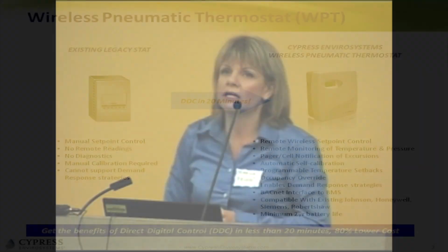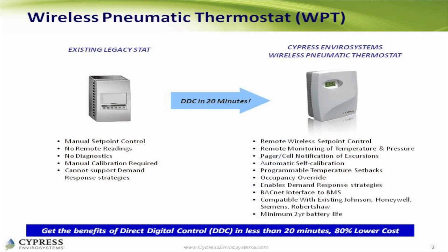So we developed the wireless pneumatic thermostat, which is really a hybrid. It keeps the pneumatic control that's behind the wall, so that all the control air that's going to the ducting behind the wall stays in place. The replacement of the thermostat is very simple. You take the existing pneumatic stat off the wall, there's control air behind there, those tubes are connected to the back of our new wireless pneumatic thermostat, and all that control air continues to operate the way it has for the last 20 or 30 years.